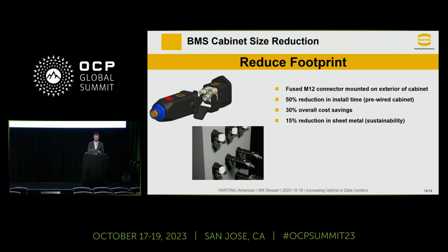This is a really cool solution, we call it the Han Protect. It also has a light — a red light that lights up when the fuse is blown. So you can see from the outside if your cabinet's not working and your PLC is giving you an alarm, you can tell externally that the fuse has blown and replace it easily with whatever labor is available.